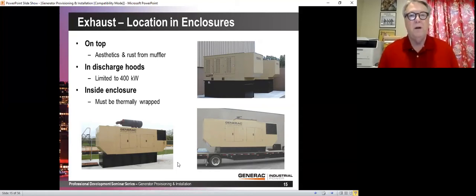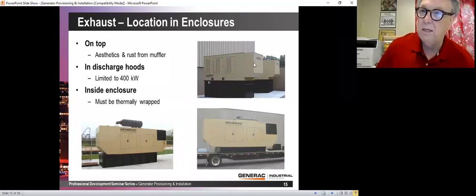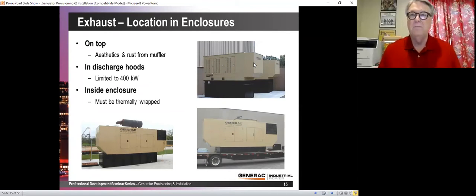In the lower left, we've got our standard with the muffler on top, and that doesn't even look good when it's new. But typically, the first part to rust is going to be that silencer on top. And then the exhaust from the silencer is right there on top. It doesn't come out at a high velocity. It's really better to put that in an exhaust scoop like we have in the upper right-hand corner here, and then you can't see the muffler, and the smoke or the particulate that comes out of the engine is going to join with the airflow through the generator itself that's cooling the generator, and it exhausts at quite high velocity and blows it up into the air.